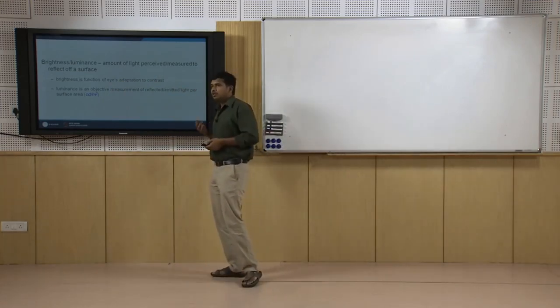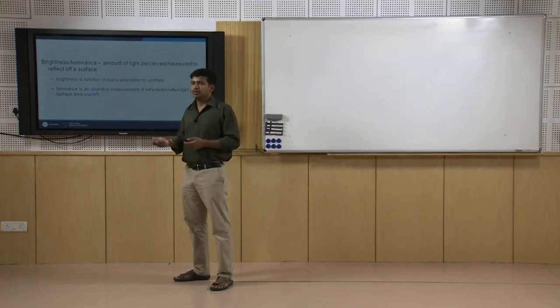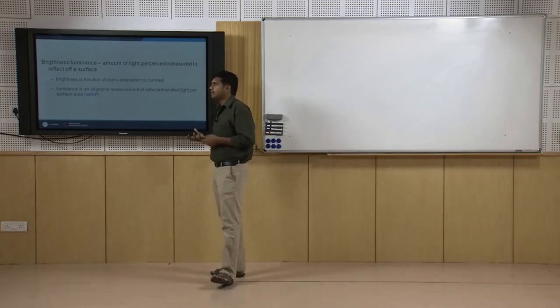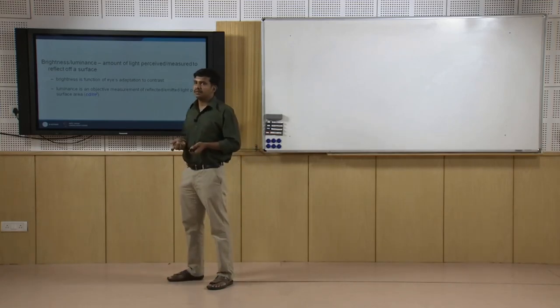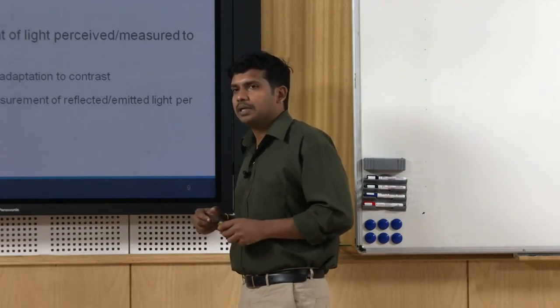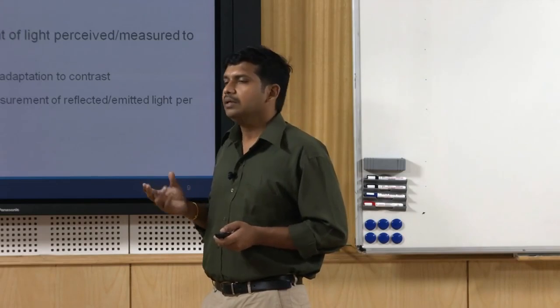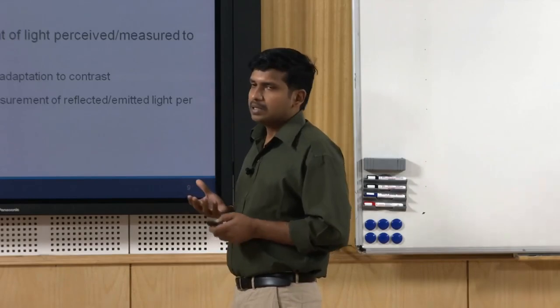This is referred to as brightness or luminance level, measured as candela per meter square. Lux levels can be measured with inexpensive illuminance meters or lux meters. For luminance, there are specific devices where you focus on a particular surface, set the surface properties — like a camera — and they are slightly pricier devices, giving you the brightness level or luminance of a surface.